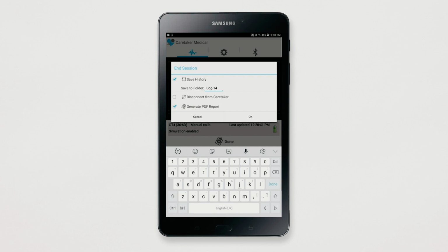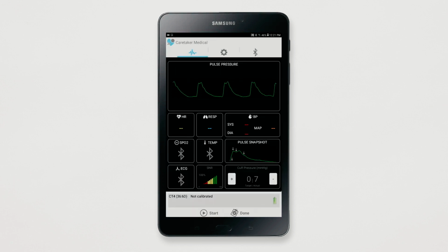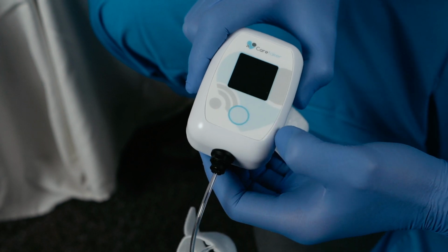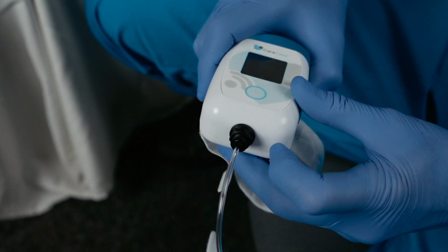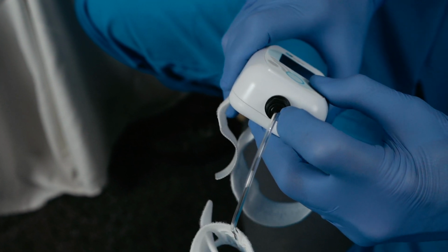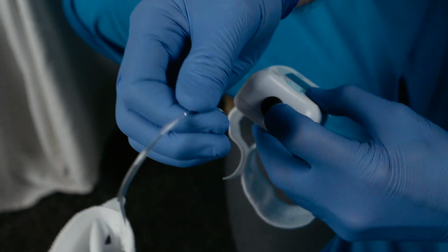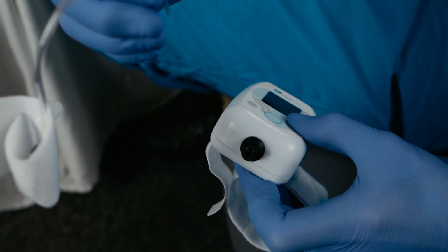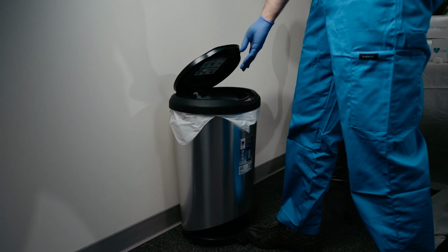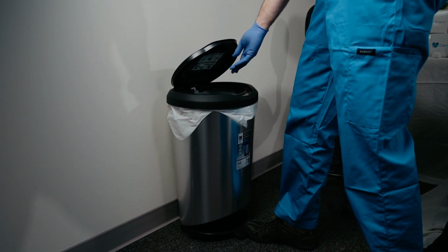After a session is concluded, you may still see a waveform on the tablet. This is because the tablet is still connected to the wrist device, but no information is being stored at this time. Now, power off the wrist device simply by long pressing on the button. Disconnect the tube from the nozzle of the wrist unit by depressing the ring collar and pulling. Discard the disposable finger cuff and wrist strap and clean the device with an aseptic wipe.